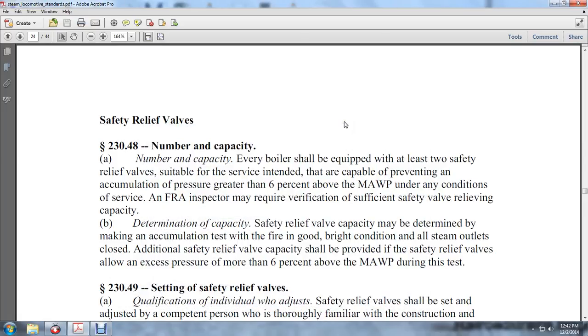230-48: Safety relief valves — number and capacity. Each boiler shall be equipped with at least two safety relief valves suitable for the service intended, capable of preventing accumulation of pressure greater than 6 percent above the MAWP under conditions of service. An FRA inspector may require verification of sufficient safety valve relieving capacity.